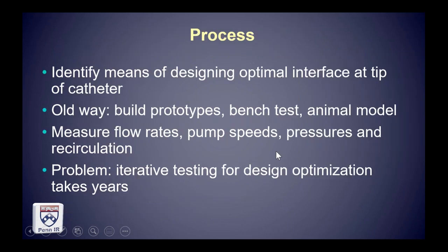In solving this problem, you identify the means of designing the optimal interface of the tip of the dialysis catheter. The conventional way was to build a bunch of prototypes, test them in a bench model of hemodialysis at flow rates of 400 milliliters per minute, iterate to the optimal model, test in an animal model, and then move on to a clinical catheter. You would measure flow rates, dialysis pump speeds, arterial and venous pressures within the dialysis circuit, and recirculation.